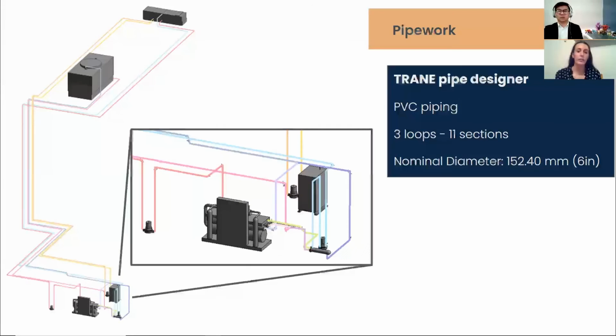Pipework is sized using TRANE Pipe Designer, where the three hydronic loops were separated into 11 sections. The results showed that 6-inch PVC pipes will be required for all sections. PVC was chosen since it's recyclable and an environmentally friendly product that is light, durable, and cost-effective.